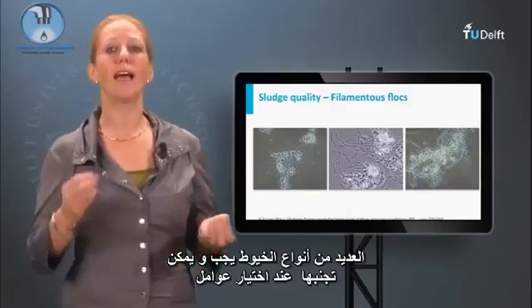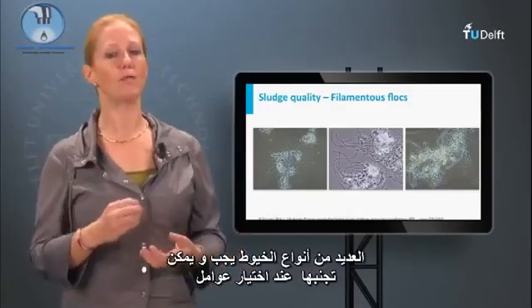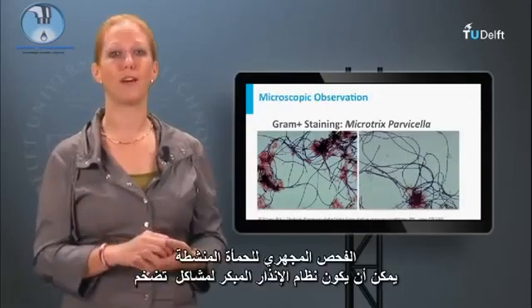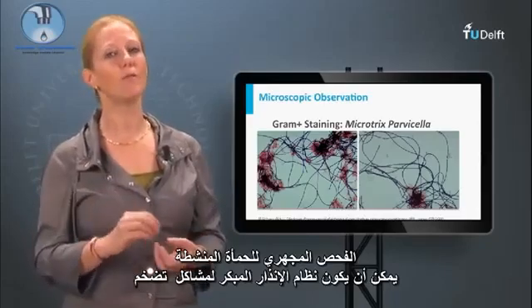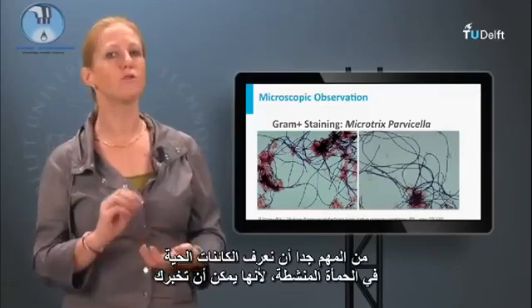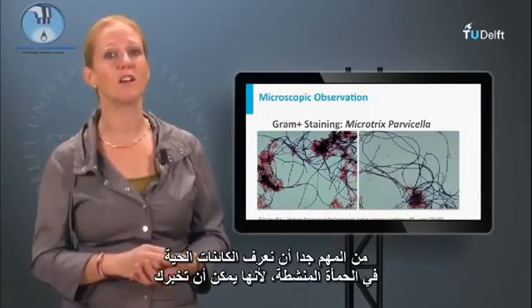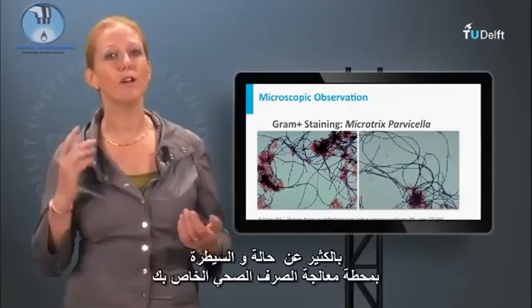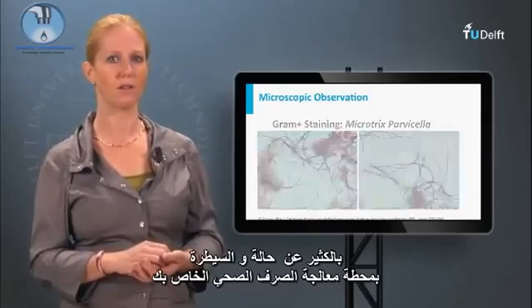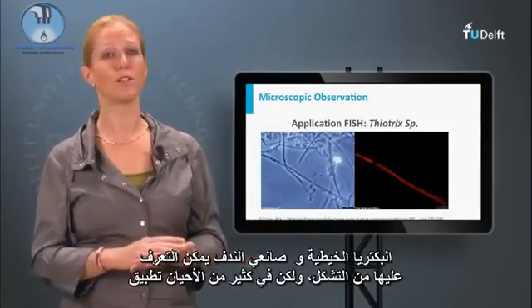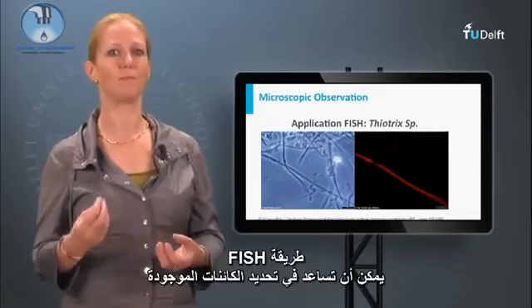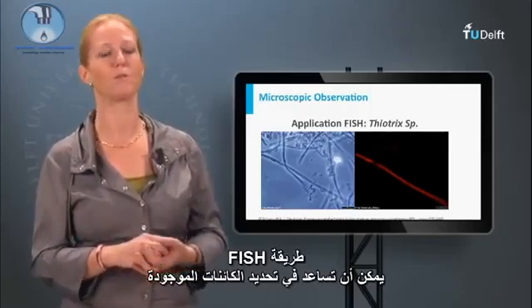Many types of filaments should and can be avoided when the right process parameters are chosen. Microscopic observation of activated sludge can be an early warning system for bulking sludge problems. It is very important to recognize the organisms in the activated sludge, since they can tell you a lot about the condition and control of your sewage treatment plant. Filaments as well as flock formers could be recognized on morphology, but often applied FISH methods could help identifying the microorganisms present.